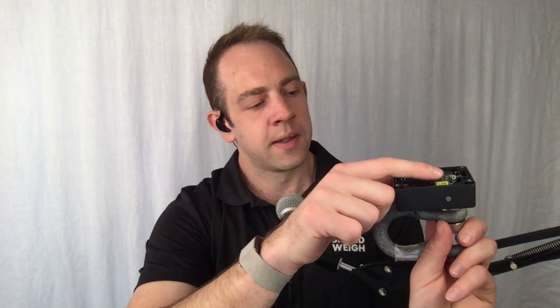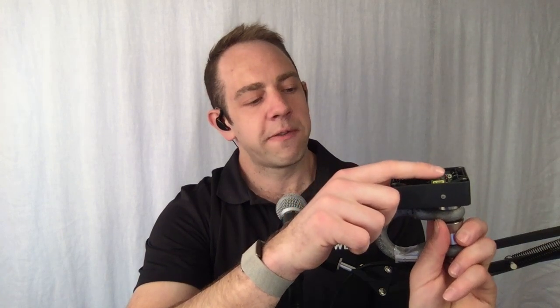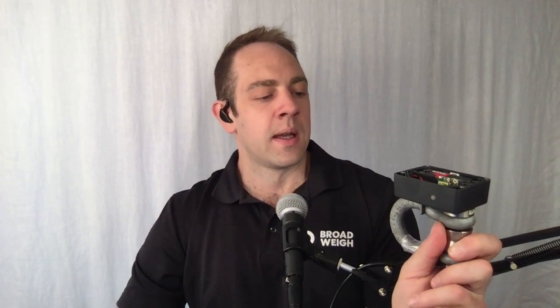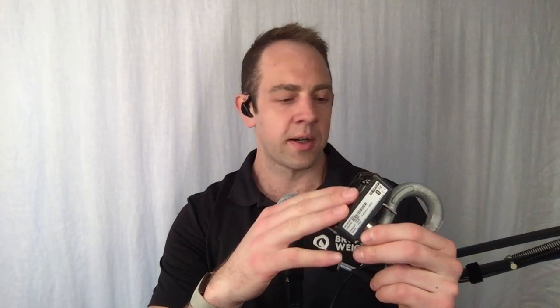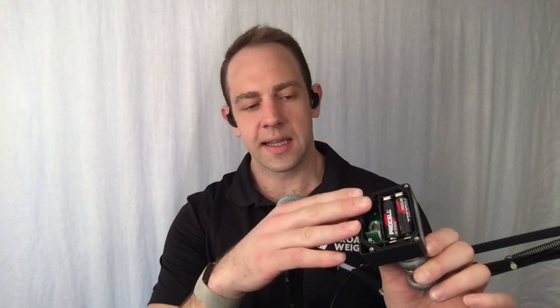The one thing about the Bluetooth items, once they're powered, you'll see this little flashing LED on the inside. I don't know if you can see it on the video. That will be flashing, as well as this outside light. That is flashing at the sample rate of what we're transmitting data. The Bluetooth load cells do not shut off. So once they're powered, they're always transmitting. We're going to talk about the configuration, how to set up a project in this video. In a separate video, we're going to be talking about the configuration of any of these settings within the load cell. How we're going to pair into that, re-zero the cell, any of those items. So follow along for this first video, check out the next video when that releases, and hopefully this should get you going on your new Bluetooth load cell.